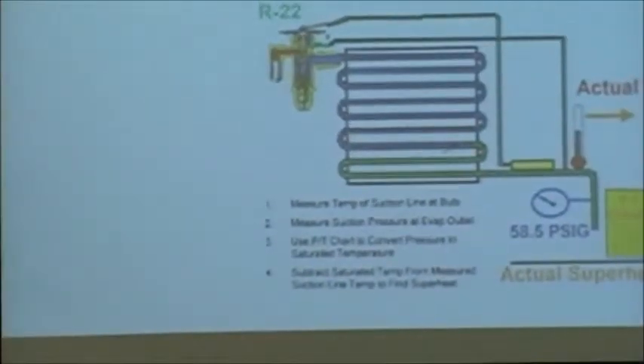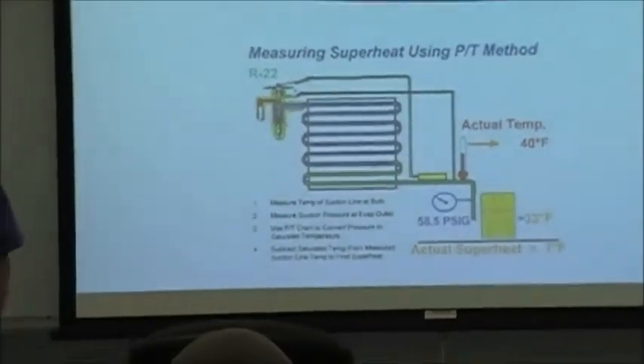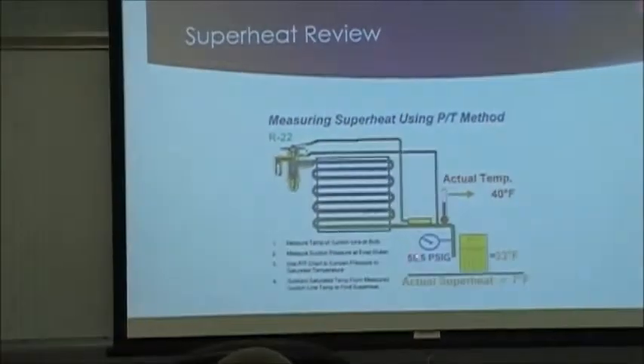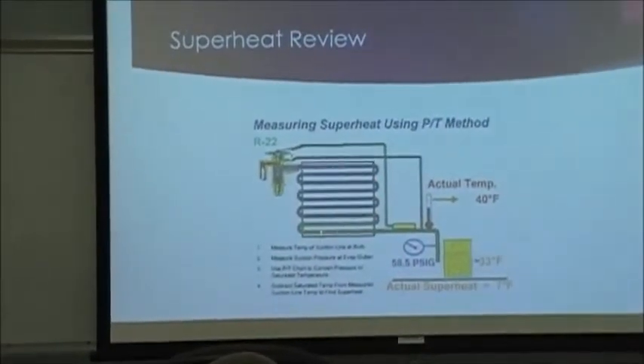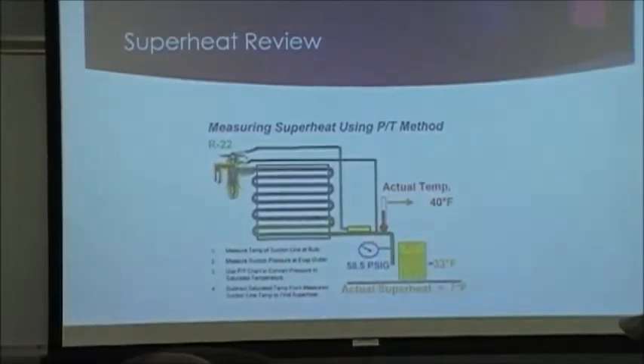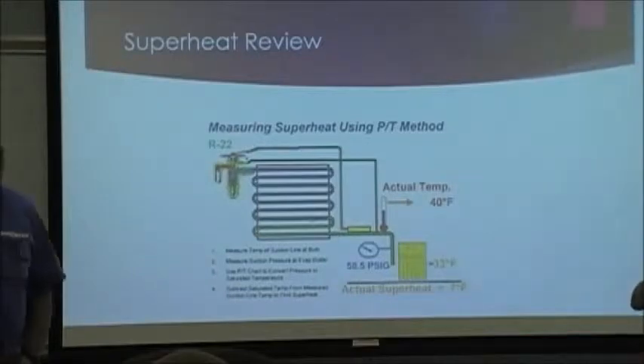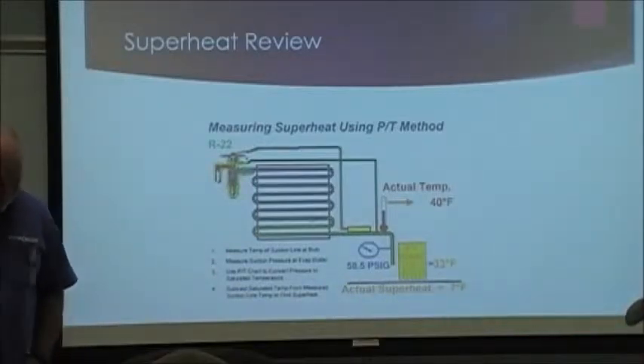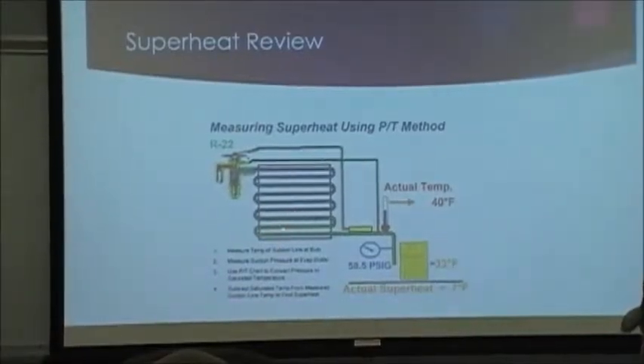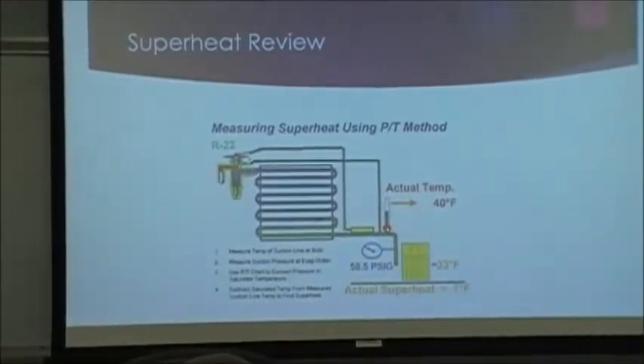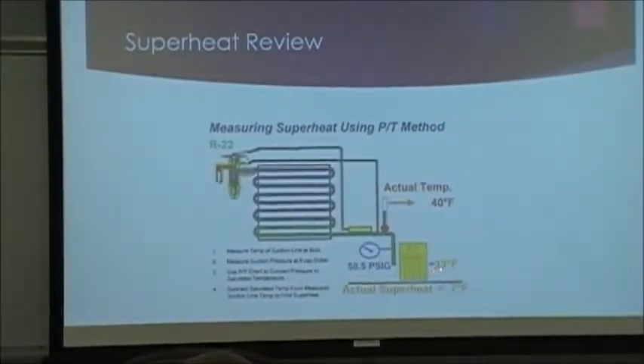Heat that's added to or above that saturation temperature is called superheat. So we know we have a 33 degree saturation temperature, and we know we have a 40 degree line right there. 40 minus 33 equals 7, so we have 7 degrees superheat.